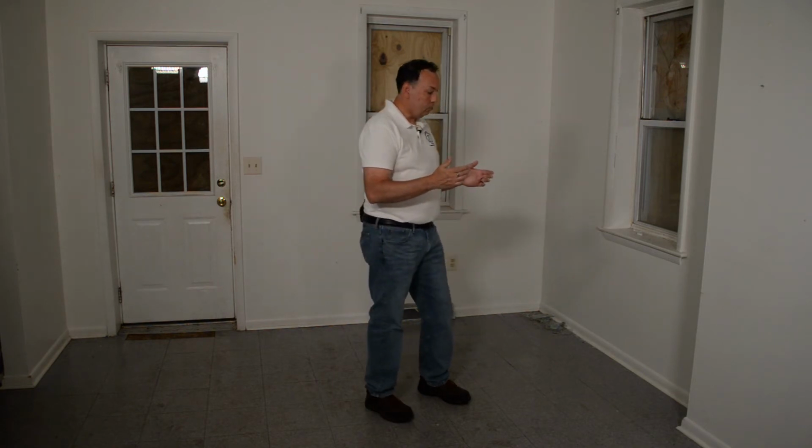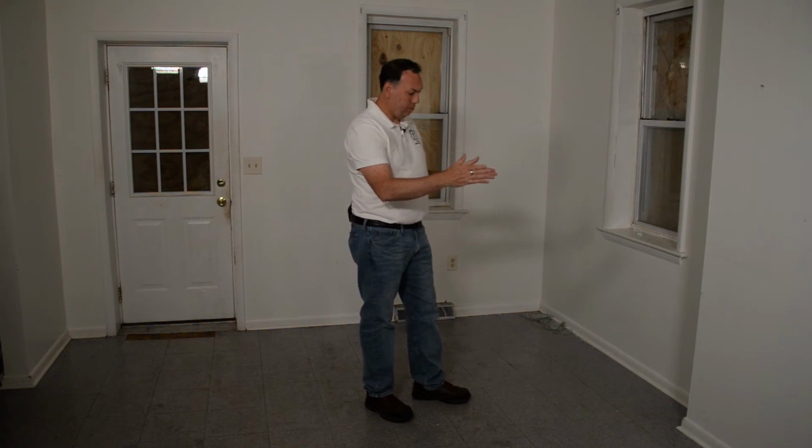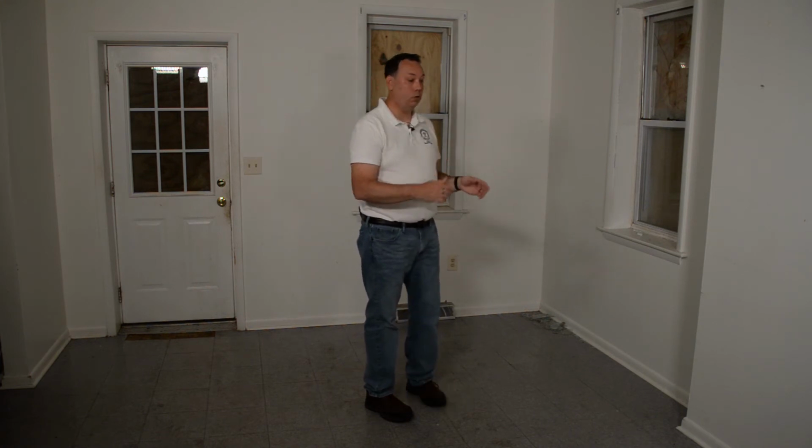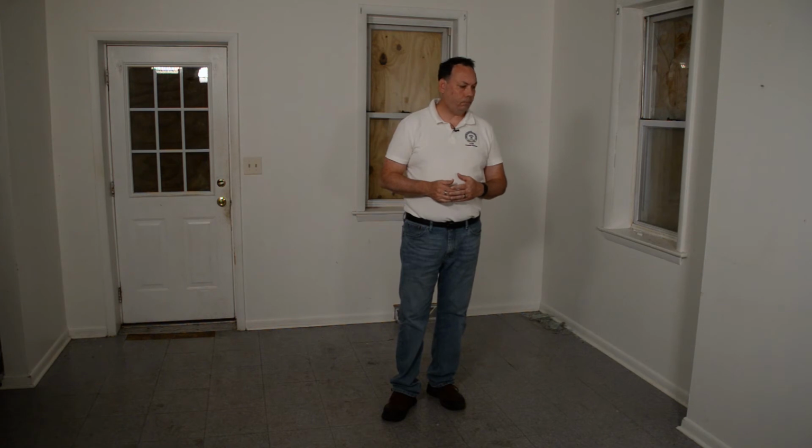Ensure that there's at least 2 remote receptacles in a room. So what you want to avoid is, to meet the requirement, sometimes what people will do is they'll put 2 receptacles in real close proximity of one another, but that's not separate and remote. So you would have a receptacle over here, and then you would have a receptacle over here to meet that requirement. And just making sure, again, that they're working properly, they're properly grounded. So I'm going to have a device where I can test it to make sure it's working correctly. There's no open grounds and so forth.